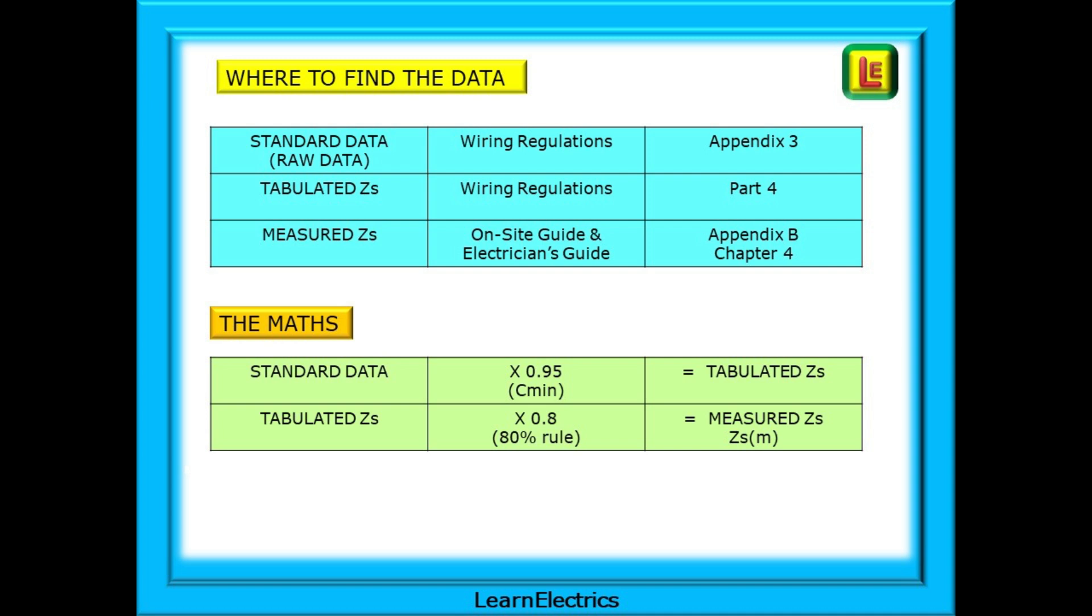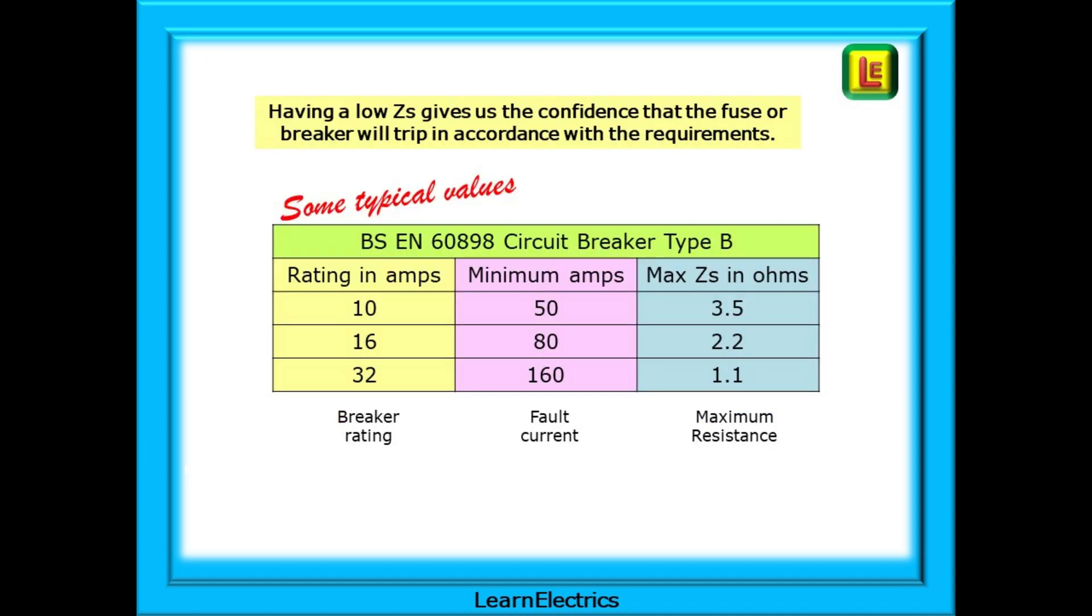Sometimes, but not always, watch out for that one. Having a low measured ZS gives us the confidence that the fuse or breaker will trip in accordance with requirements. The lower the actual ZS, the better. Lower resistances help guarantee that a high fault current will flow.